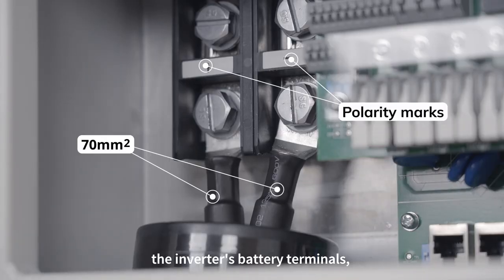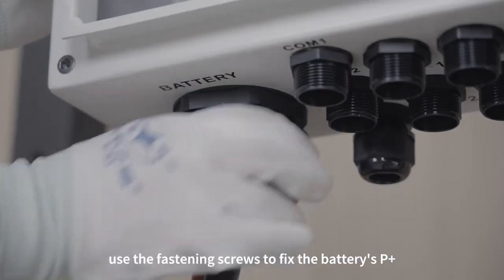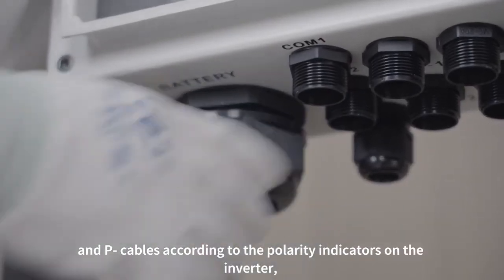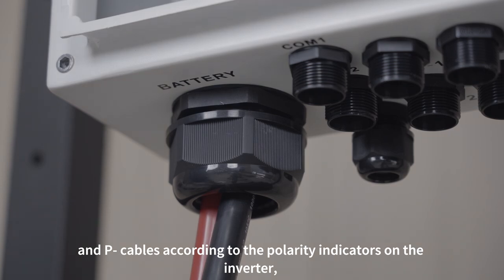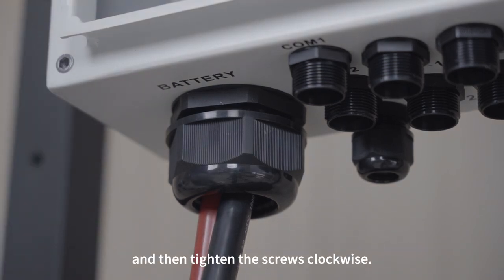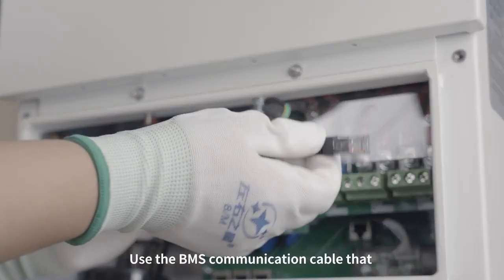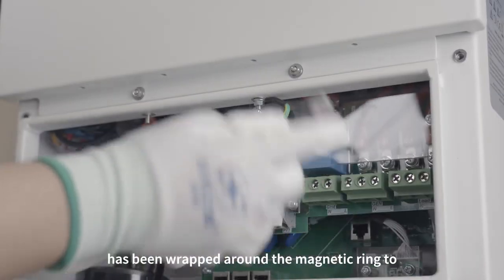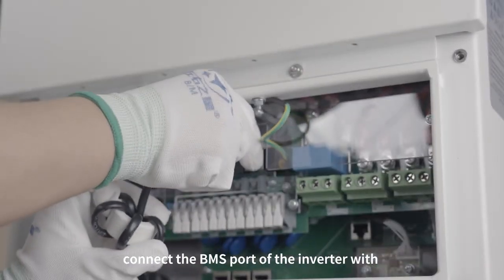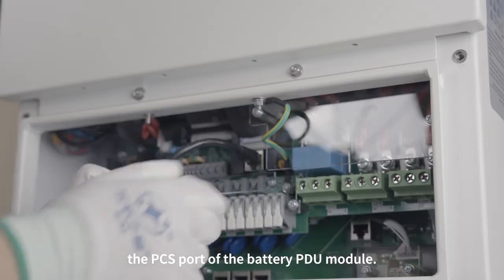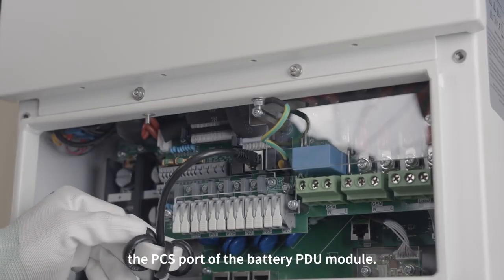Unscrew the fastening screws on the inverter's battery terminals. Use the fastening screws to fix the battery's P+ and P- cables according to the polarity indicators on the inverter, and then tighten the screws clockwise. Use the BMS communication cable that has been wrapped around the magnetic ring to connect the BMS port of the inverter with the PCs port of the battery PDU module.